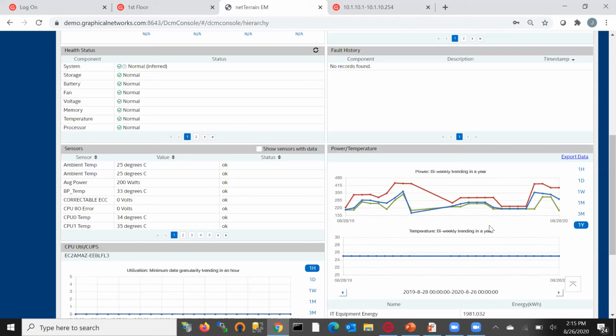And then when you start to see these trends, you can start to do things about it, and either take devices that you don't want to exceed a certain threshold, maybe control the power if it's a server, or just monitor it. Because if you do have problems in the data center with power, you have limited power, and you can't add more for whatever reason, it's just an older data center, then you might need some more granular ability to track that power and understand what you have and then make decisions.